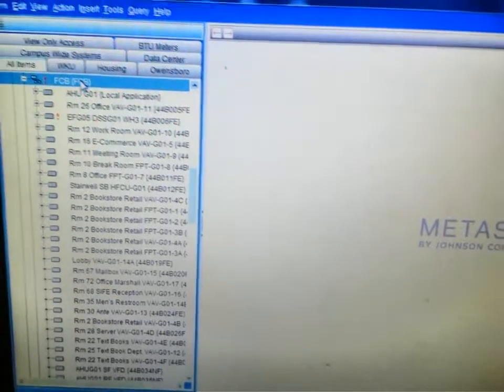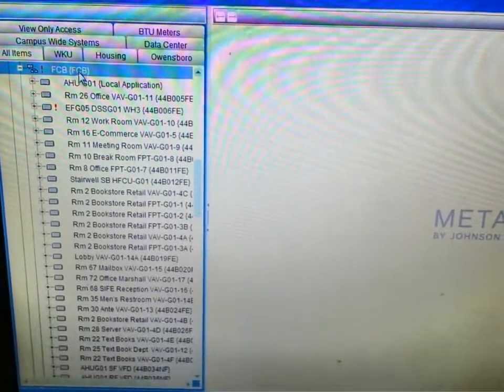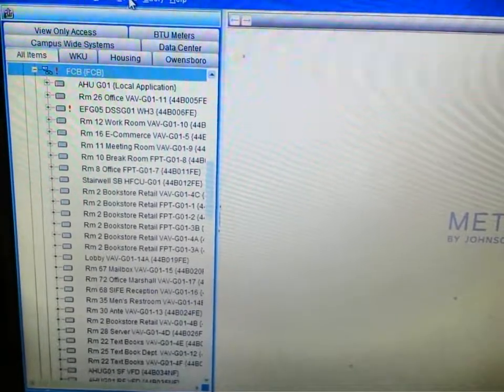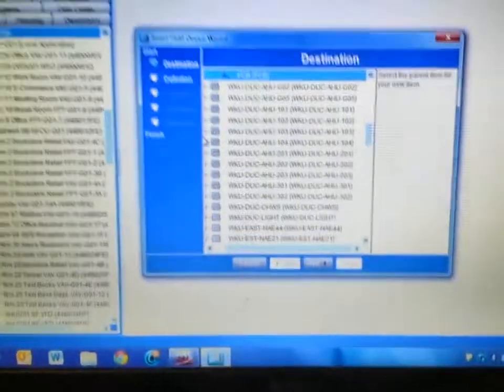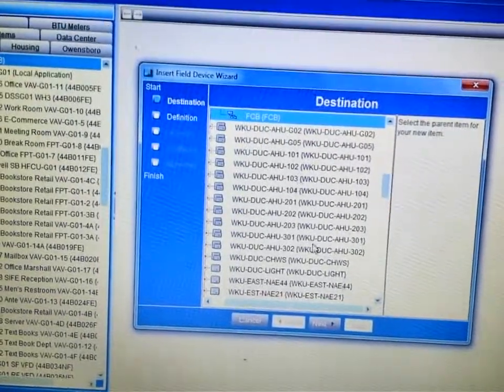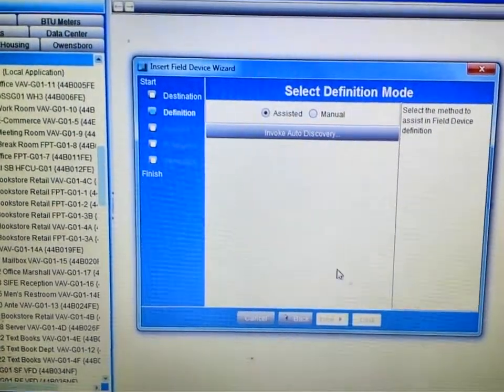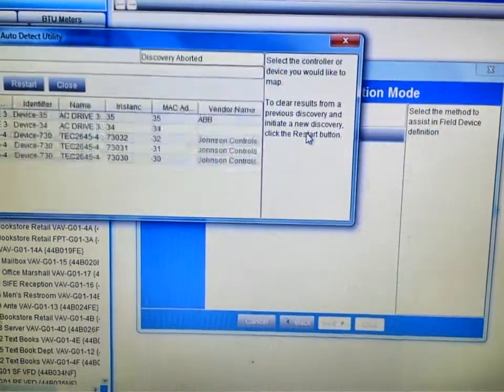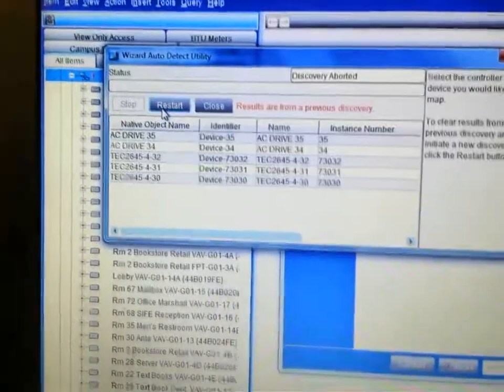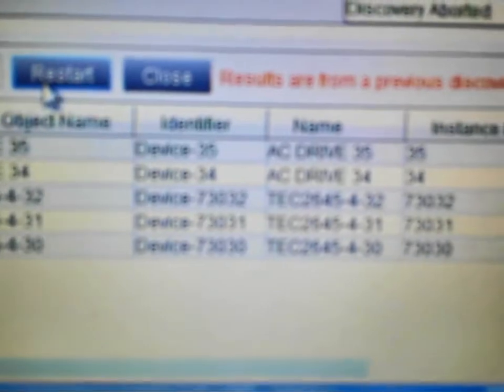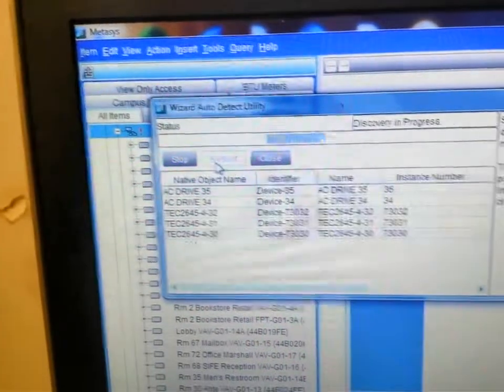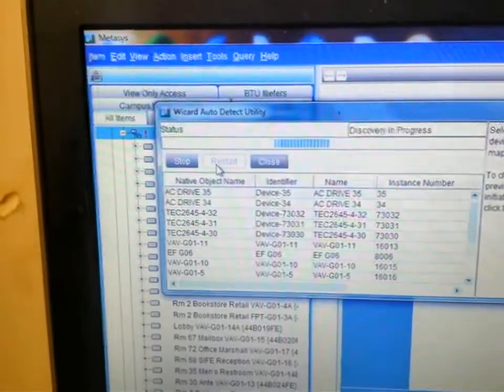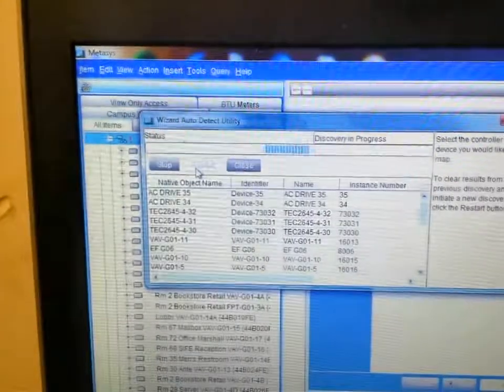Now that we have our meter connected and all of our settings configured correctly, we are ready to try to add this to our network. We highlight the particular trunk that we are going to add it to, go up to Insert, then Field Device. The great thing about BACnet is the auto-discover feature. This screen gives me a review of where I am putting that device, so I click Next, and here we go with the auto-discover. If you get a screen that tells you the results are from a previous discovery, press Restart — since you are adding a device, you do not want it to use past results. You want it to go out and look at that network from the ground up. So we are going to let this run and see if we can find that meter.